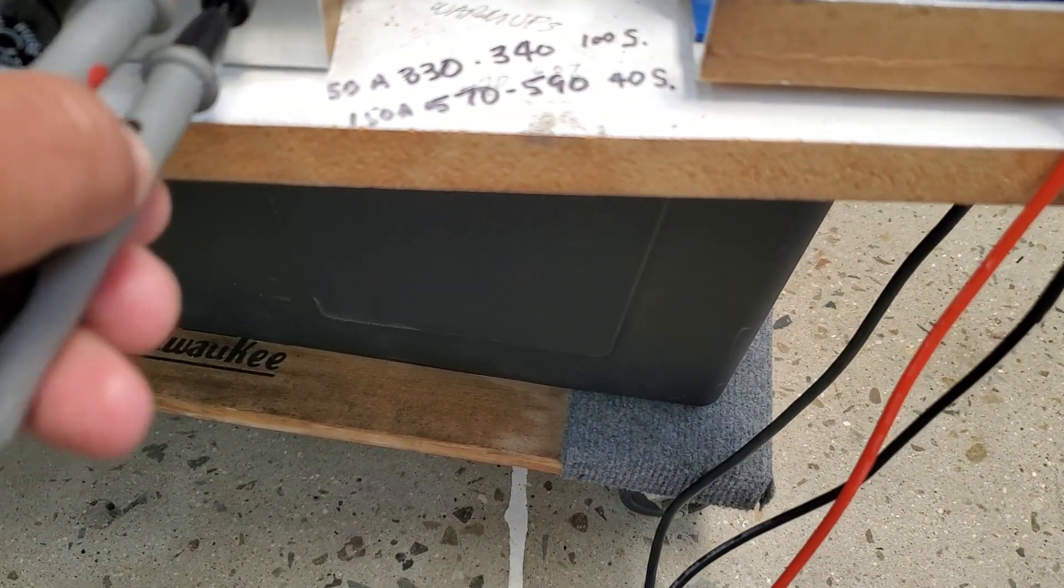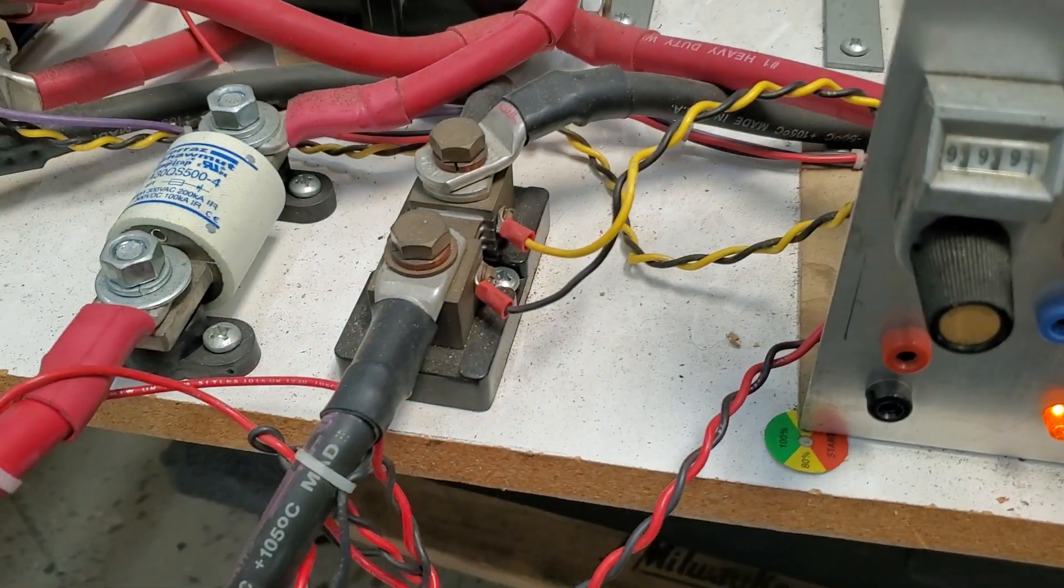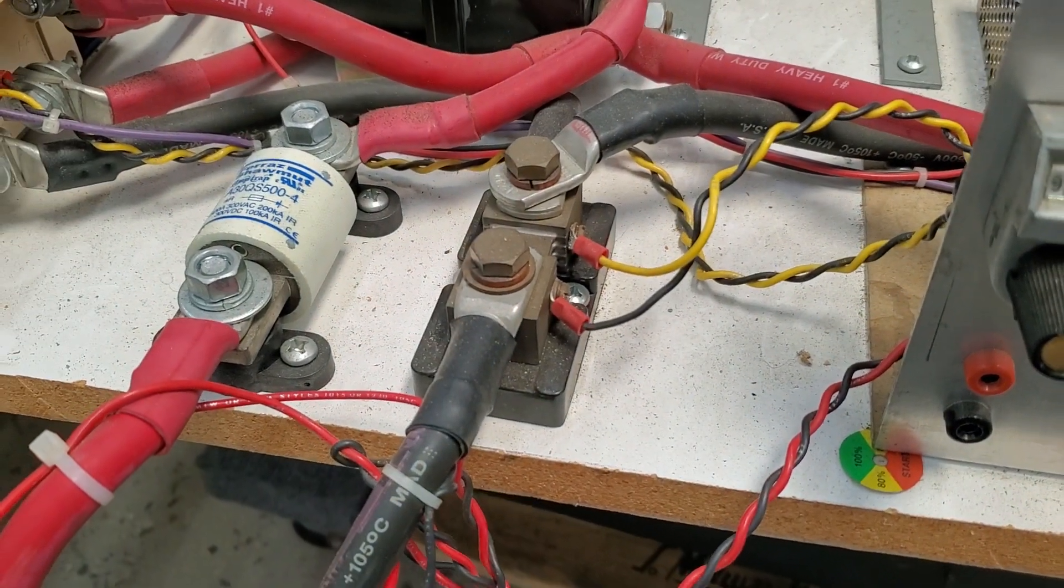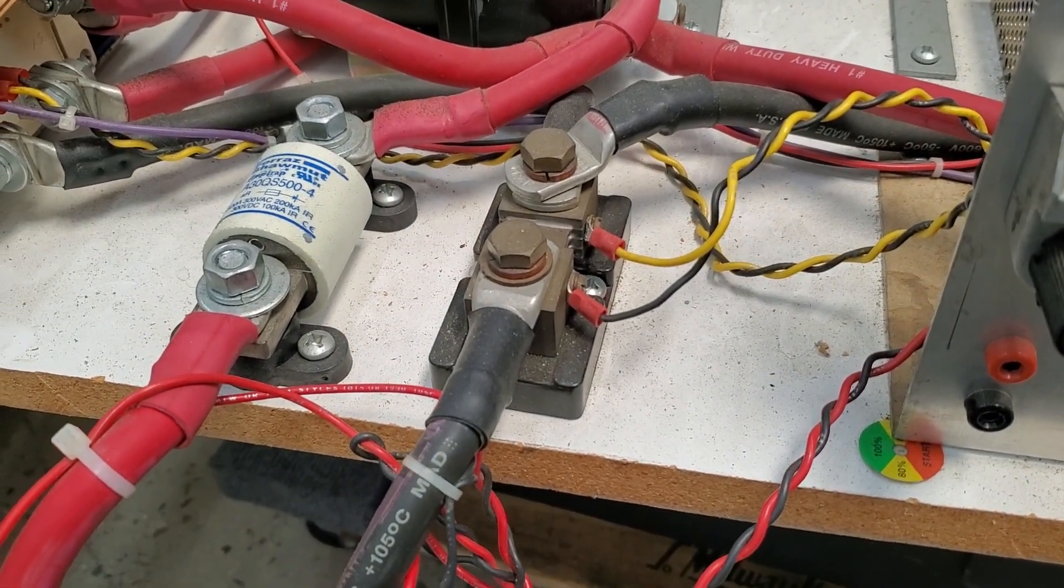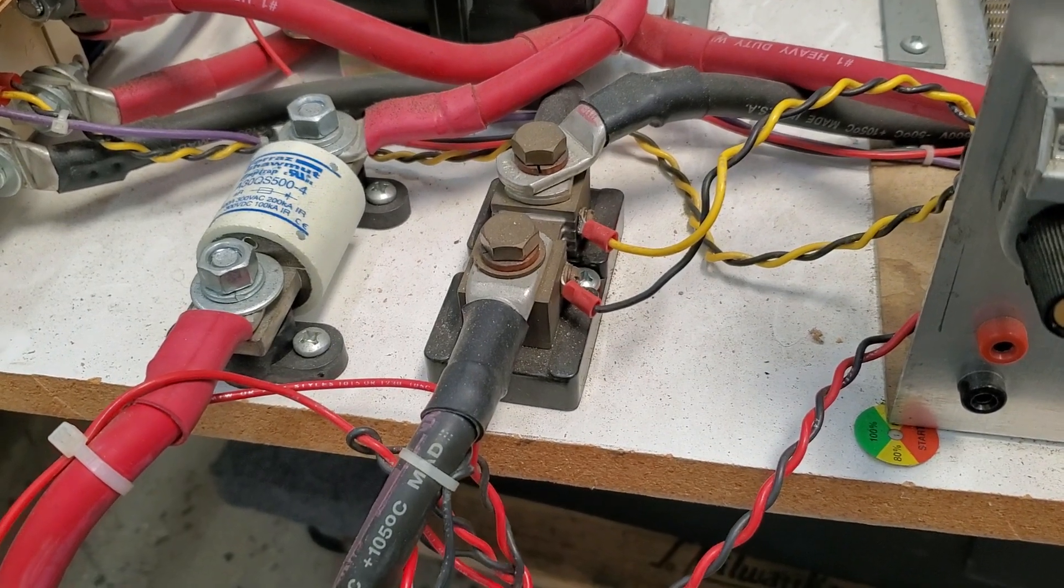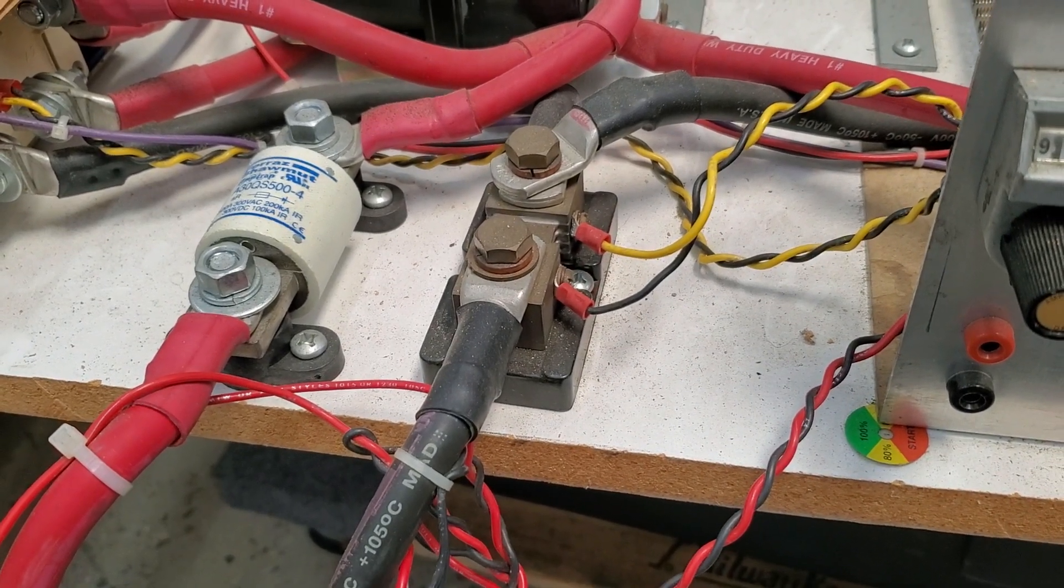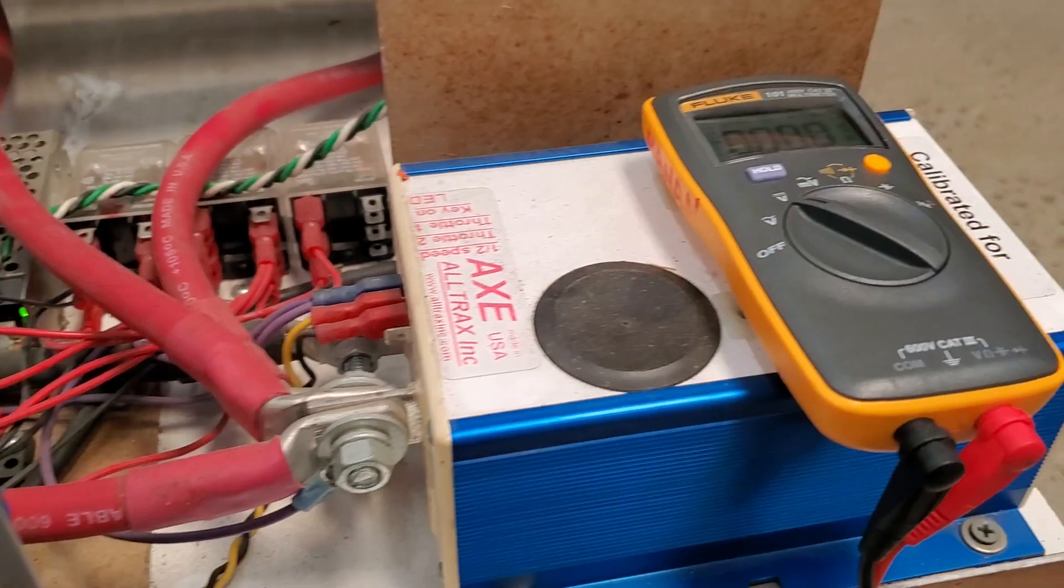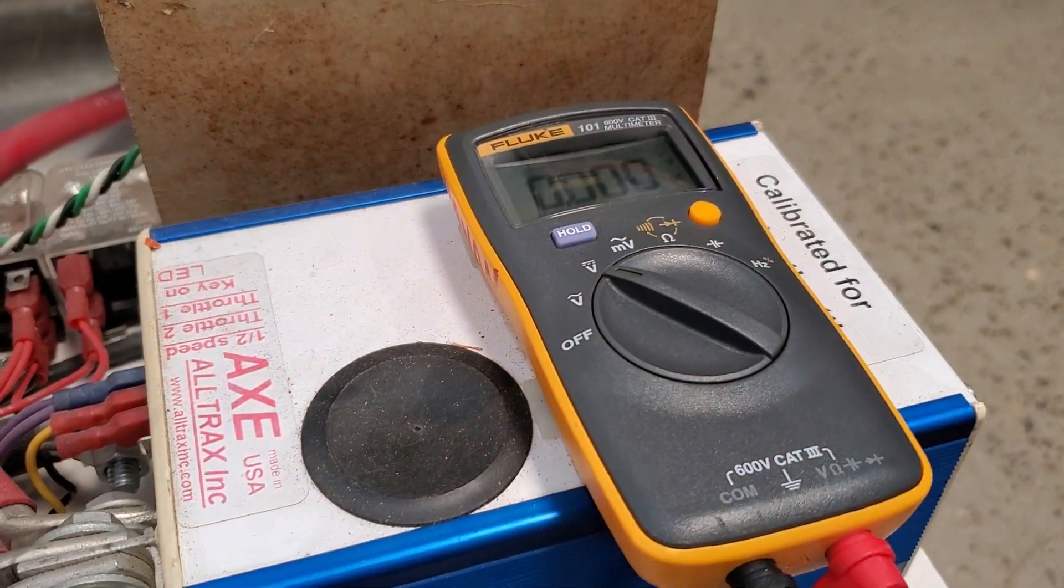This port here tells me the current because it's the voltage drop across this resistor which appears to say it's 50 millivolts at 500 amps which is its maximum rating. So it's at zero right now.